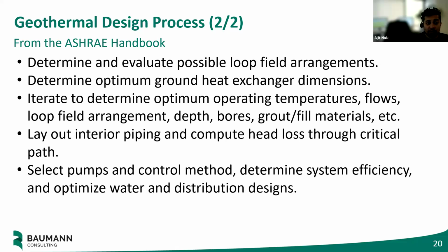It's important to note that the wells are what drives the cost. These can be $10,000 to $15,000 each, so if you need 50 wells at 15K a well, that's quite a bit of money. Optimizing to reduce your wells is always better, and it's typically cheaper to drill one deeper well than two shallower wells. There are lots of cost considerations that can affect this.